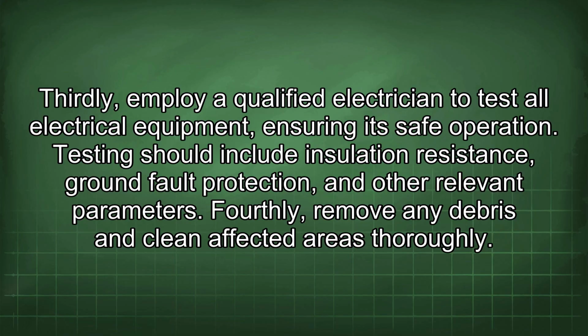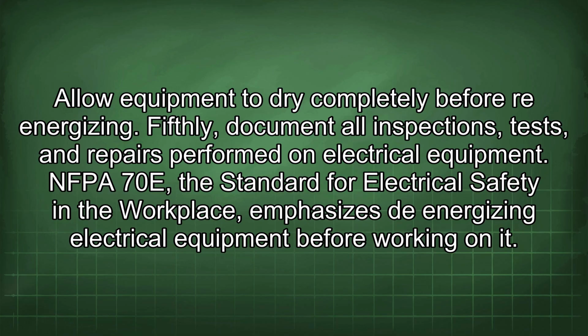Fourthly, remove any debris and clean affected areas thoroughly. Allow equipment to dry completely before re-energizing. Fifthly, document all inspections, tests, and repairs performed on electrical equipment. NFPA 70E, the standard for electrical safety in the workplace, emphasizes de-energizing electrical equipment before working on it.